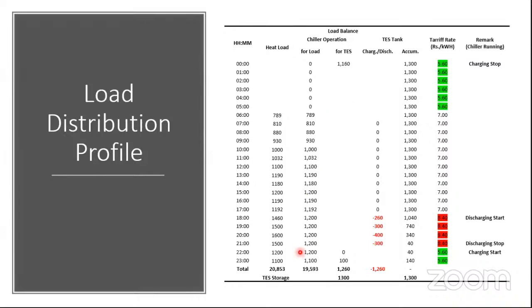This is a typical load profile for one of the projects we did, and here the peak load is 1600 tons. There was going to be a four chiller configuration, 4 into 400 tons. However, it was opted that a thermal energy storage system would be used, and three chillers, each of 400, were used, and the balance 400 tons load was passed on to the thermal storage. So this was nearly the thermal storage capacity, and nearly 1300 ton hours was the thermal storage capacity.